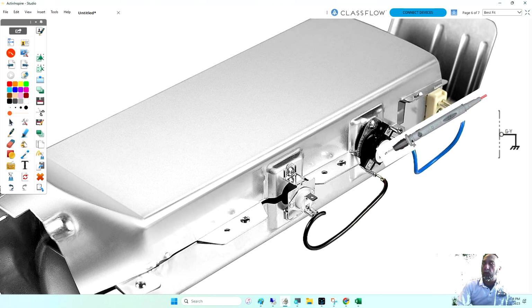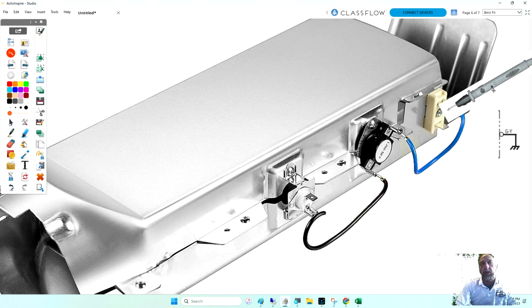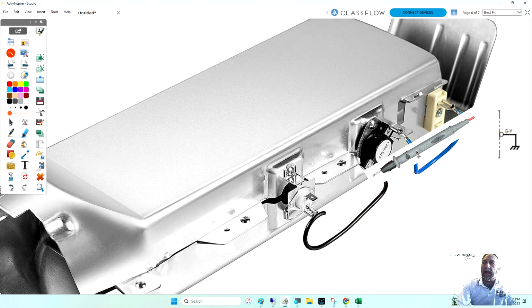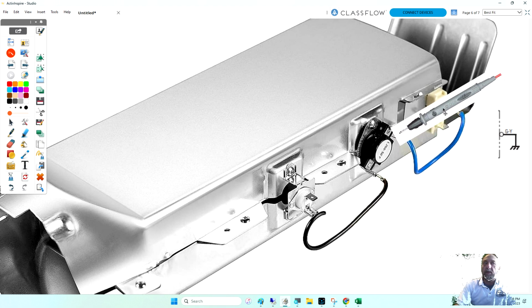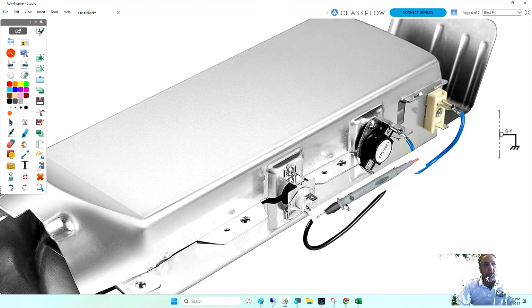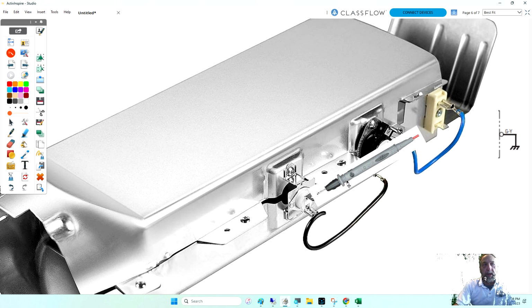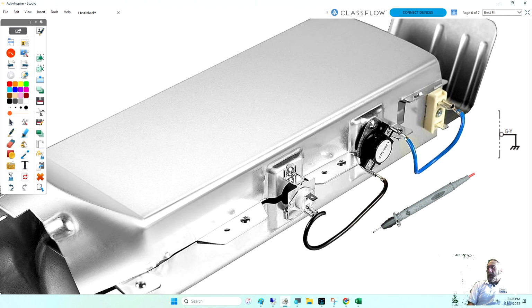If the thermostat was bad, I go here, no voltage. I'm leaving this one on the bottom one. I don't have them both here. No voltage here. No voltage. And then I go to the other side of the thermostat and I have voltage. It's coming in. It's not coming out. The problem's my thermostat. If it's my cutoff, the same thing. No voltage on the black wire. Go to the top one, I have voltage. My cutoff's bad. And that's how we find the problem. We keep going back till we find the voltage, and that's the way we can determine that.